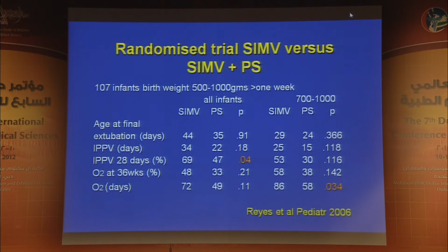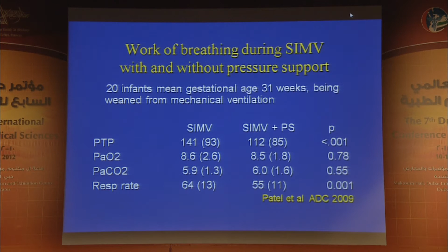And we would speculate that that is because we're triggering, the baby is receiving support for every breath, and that is reducing the work of breathing. We did a study to test that hypothesis, and we used SIMV and pressure support in exactly the same way as in Reyes' trial. We looked at 20 infants who were being weaned from mechanical ventilation, and we measured the work of breathing using the pressure time product, which I described to some of you in detail yesterday. And what you can see, in the two modes of ventilation, there are similar blood gases, but you will see that when we add pressure support, we reduce the work of breathing, and this is because the infant is breathing less. They're getting more support from the ventilator.